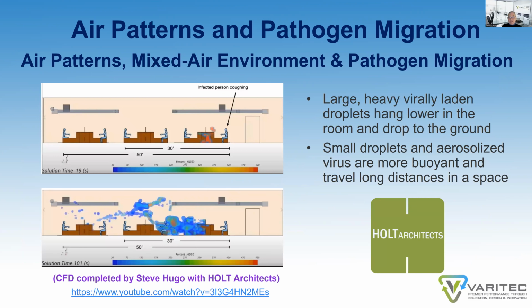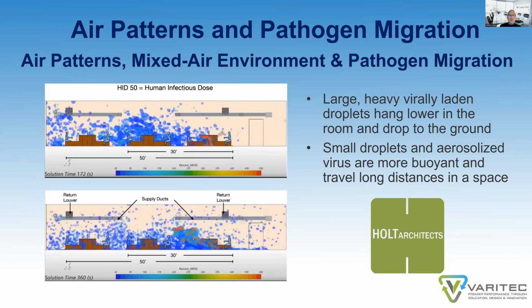There was a study done, a CFD model done by Holt Architects, that demonstrated what happens with virally laden droplets as they're expressed by an infected individual. Large, heavy, virally laden droplets hang lower in the room after they've been ejected because of their mass and weight. Gravity does its work, and it draws those droplets to the ground out of the air where they cease to be less of a hazard. Small droplets and aerosolized virus, however, are more buoyant, and they travel long distances in the space. In fact, if somebody sneezes and ejects virally laden droplets into the space, those droplets leave at a rate of 44 miles per hour, and they project easily up to 26 to 28 feet across a room if the room is large enough. Anyways, you can see a conventional mixed air system is conducive for spreading viruses.